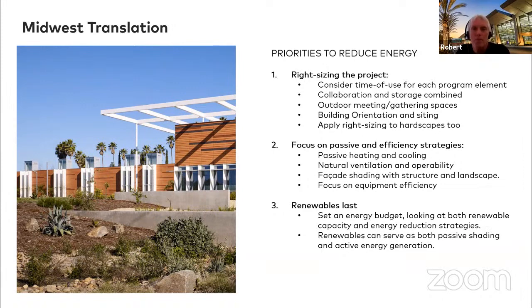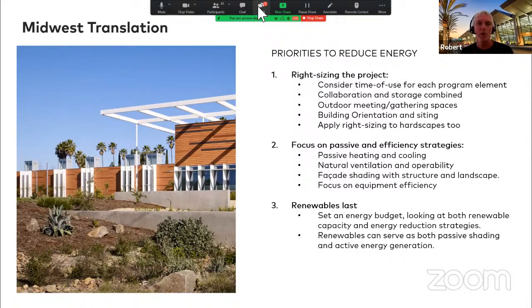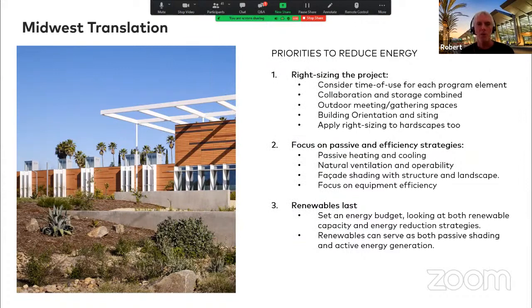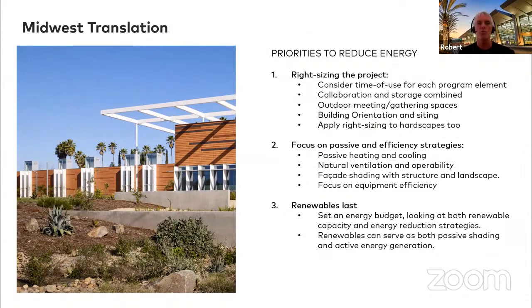Actually, that's a no. They are integral to the HVAC system, and heating, ventilation and air conditioning for this building is primarily natural, for both the administration building and the warehouse building. They both have ceiling fans, and that's just one step in the process. In the early morning, things may be closed up because temperatures are fine. Ultimately, they open the louvers at the bottom and top to let the solar chimney take effect and draw cool air through the building. As the buildings heat up, the ceiling fans then turn on as the next step, allowing air to circulate within the room.